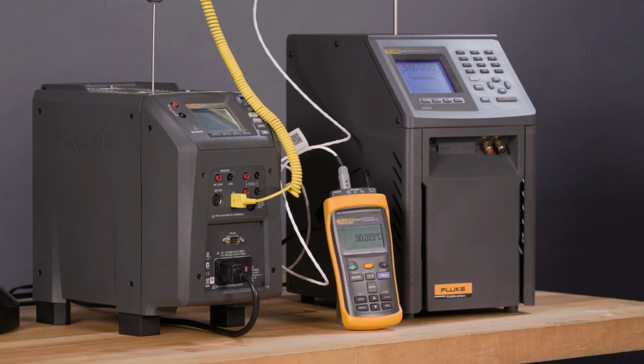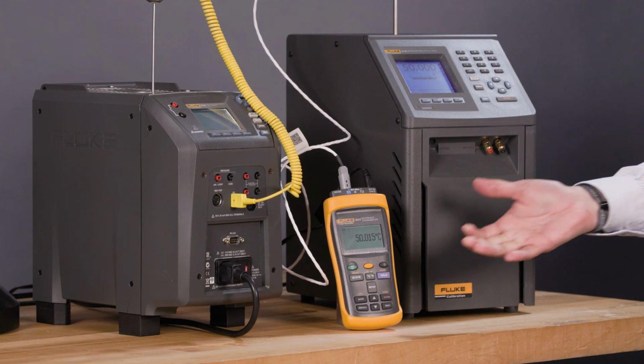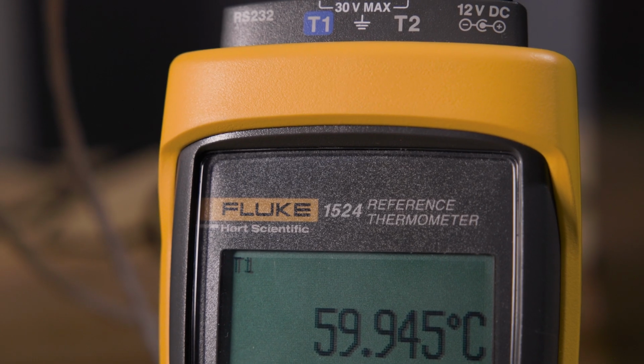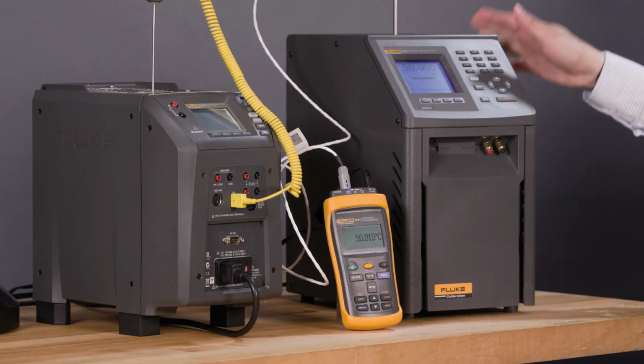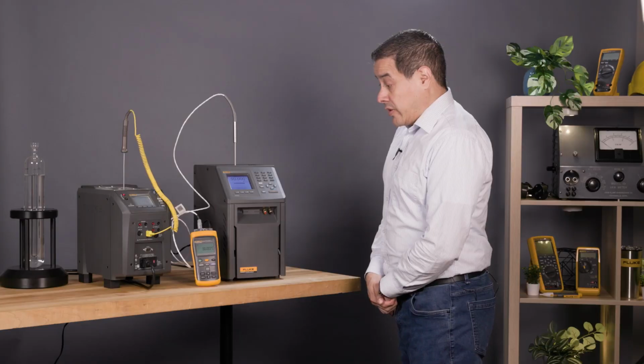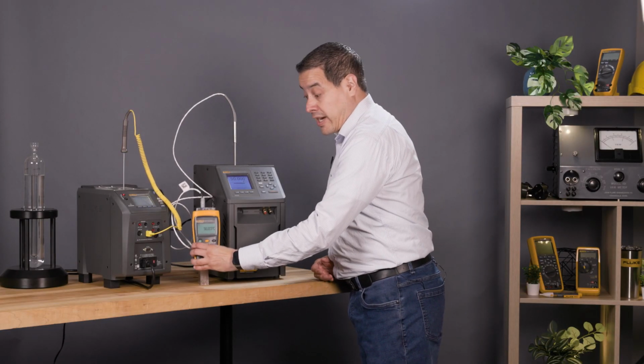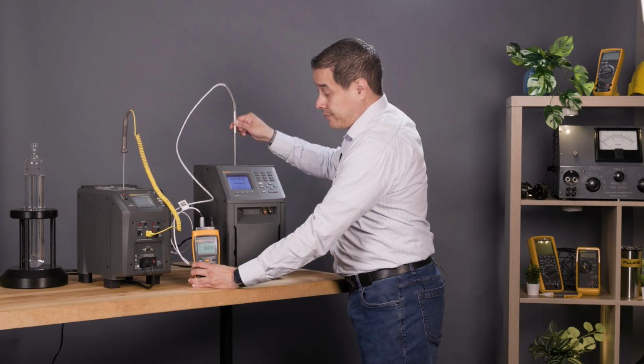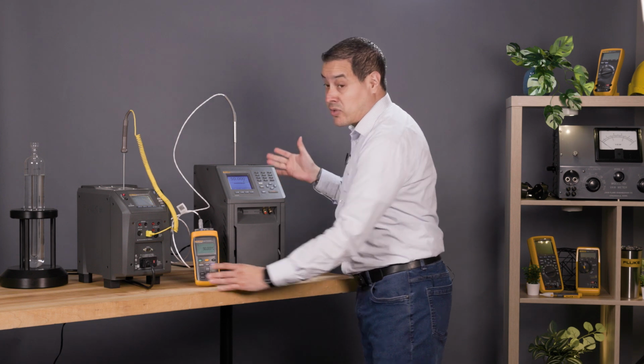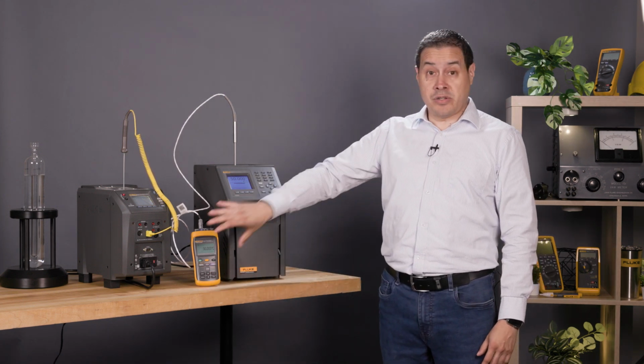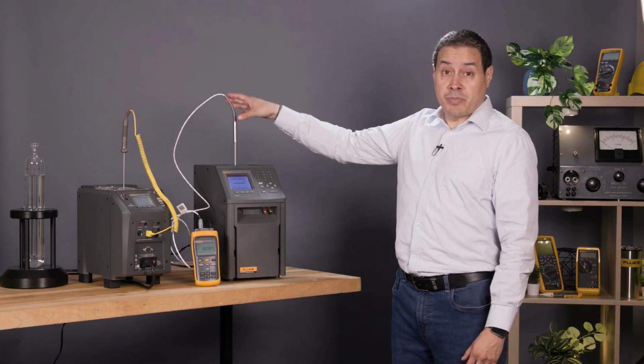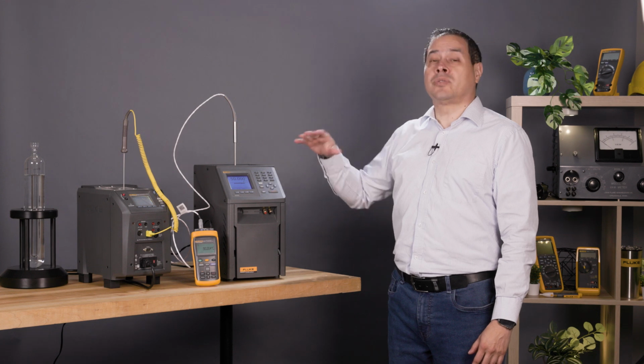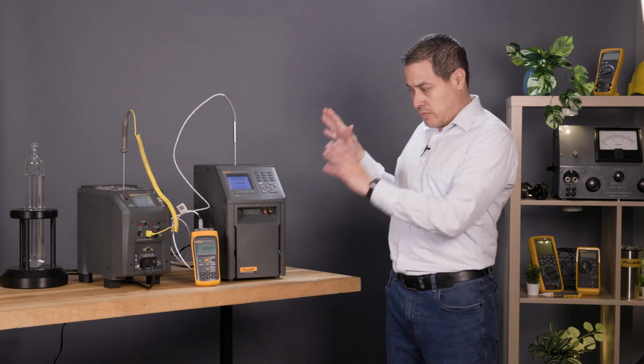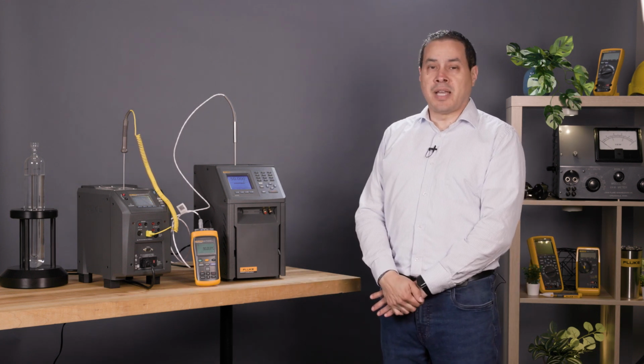Now you've read the manual, let's jump to calibrating your unit under test. In this case, a 1524 reference thermometer with a 9173 dry well. First, you notice you have an indicator, you have a probe, and then you need the dry well. This is the most common application. You're going to be calibrating your device with the probe against your dry well. There are always more applications, but we're going to be focusing on the most common application.